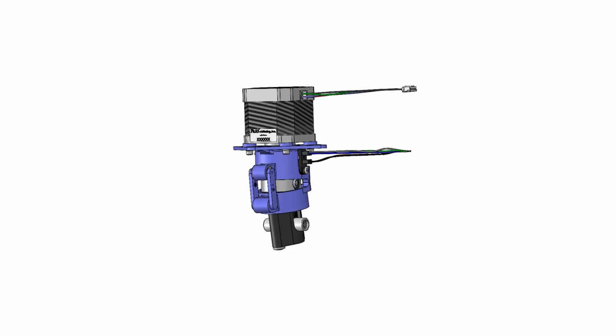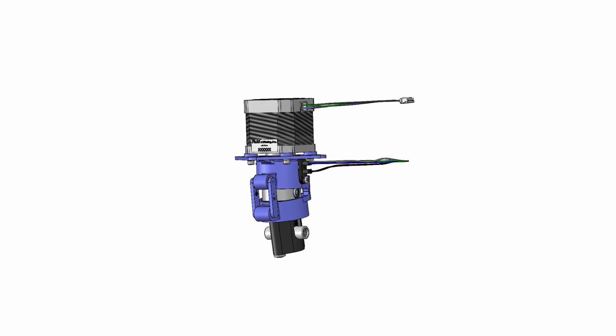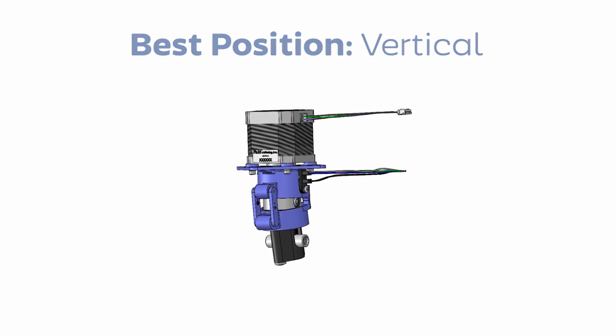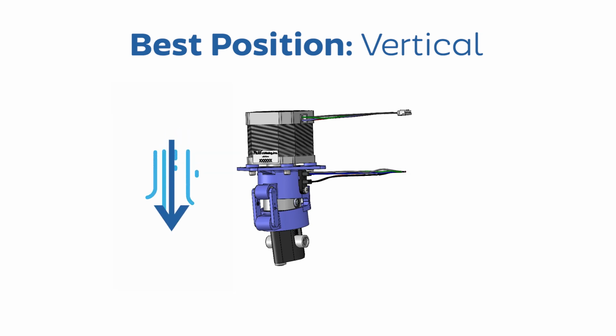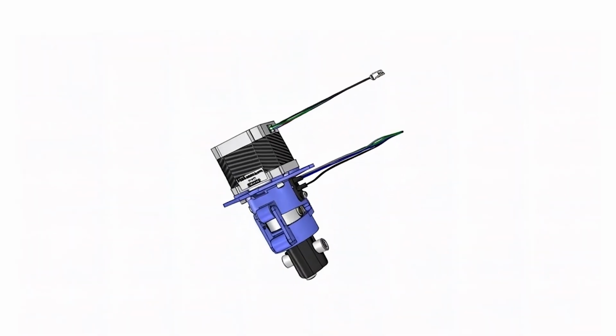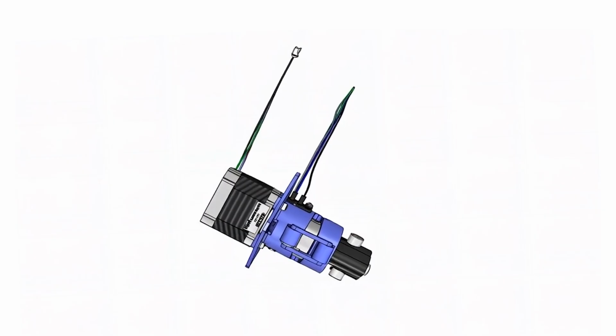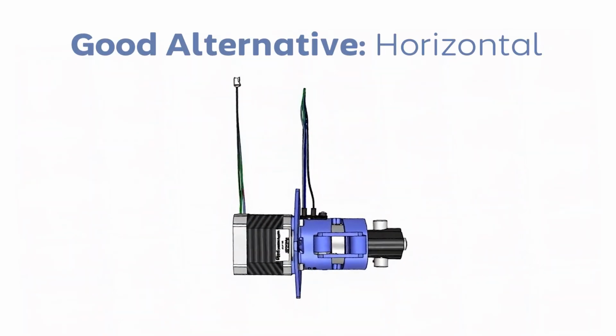Let's talk about the pump orientation, because how the pump is mounted plays a major role in how well it performs. The ideal orientation is vertical, with the pump head positioned below the motor. In this position, air is naturally pushed out of the pump, and gravity helps pull the fluid downward and away from the seals. That downward pull reduces the long-term risk of leakage. If a vertical mount isn't possible, a 90-degree horizontal rotation is also a reliable option. In this setup, the inlet should be at the bottom and the outlet should be at the top. Since air rises, that makes it easier for air bubbles to escape and keeps the pump operating smoothly.